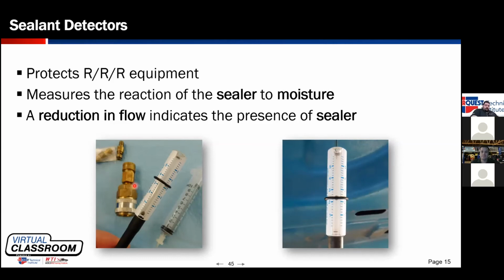You can see there's a coupler that attaches to the high side fitting of the vehicle. There's couplers available for 12, 134A, and YF. We have a brass plug. They use the little syringe, fill both sides of the brass plug with water, attach the brass plug to the coupler. The other end of the brass plug has a hose barb on it that we attach to this flow meter, attach to the high side of the system, let refrigerant start to flow, mark with the rubber band where the flow meter settles at. Walk away for 3 minutes.